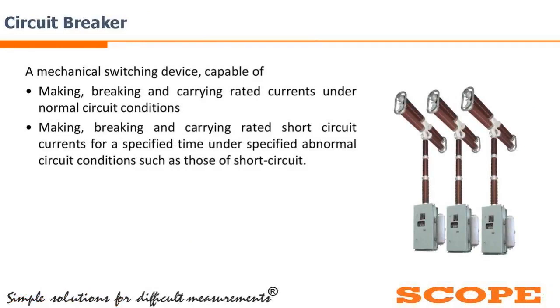Then circuit breaker. As everyone knows the function of the circuit breaker, it is a mechanical device which is capable of making and breaking, and also carrying rated currents under normal operating condition. Also, it is a mechanical device which is capable of making, breaking, and carrying rated short circuit currents for a specified time, which is 3 seconds or 1 second as per the type test, under specified abnormal condition, such as those of short circuit. That is the device which can make and break the circuit.